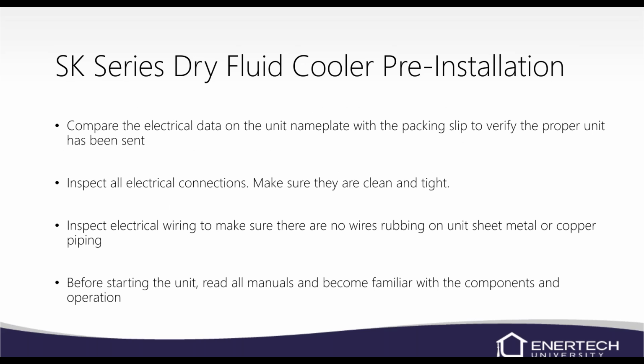Make sure you've got the proper voltage at the home, and verify that you've got the proper unit. Again, we only have 2 units, so hopefully we won't ship you the wrong unit. It doesn't happen too often, I don't think, but again, we have a 3.5 ton and a 5 ton. Make sure when you get these units, anything can happen during shipment, so check the contactors and your electrical connections and make sure that they're tight, they haven't loosened up during shipment. If they do loosen up, it causes heat to build up and wires burn up and things like that. So make sure there's no wires rubbing on the sheet metal, and copper is not rubbing on any wiring.